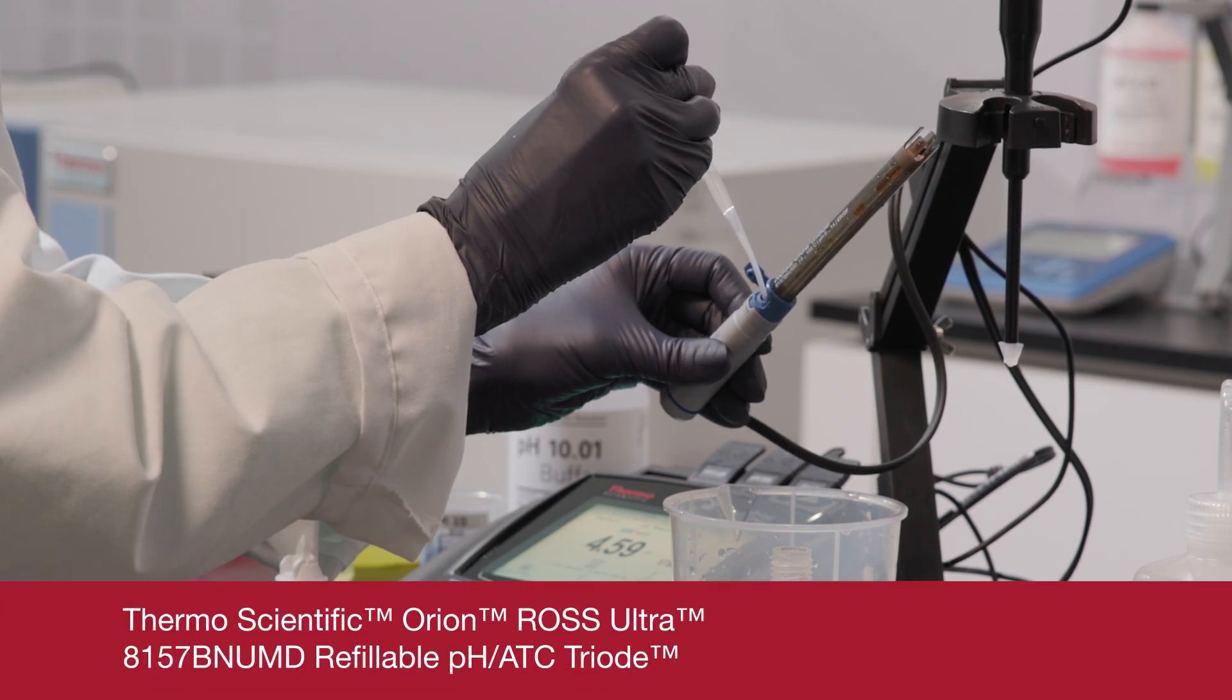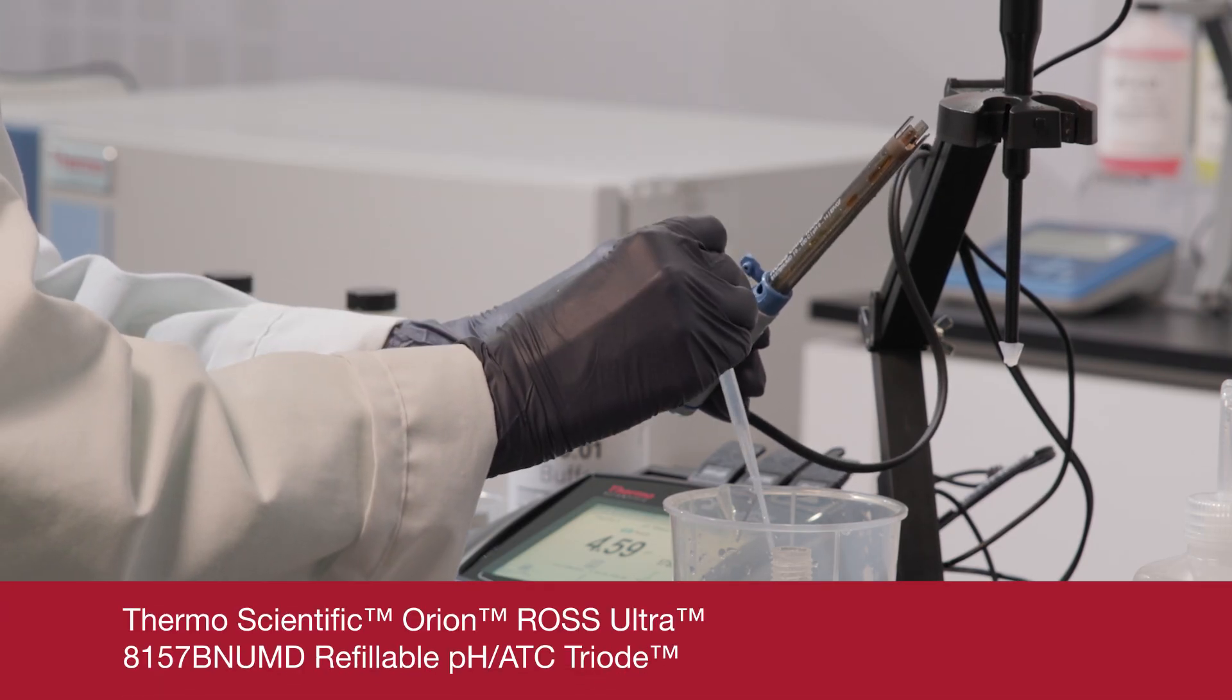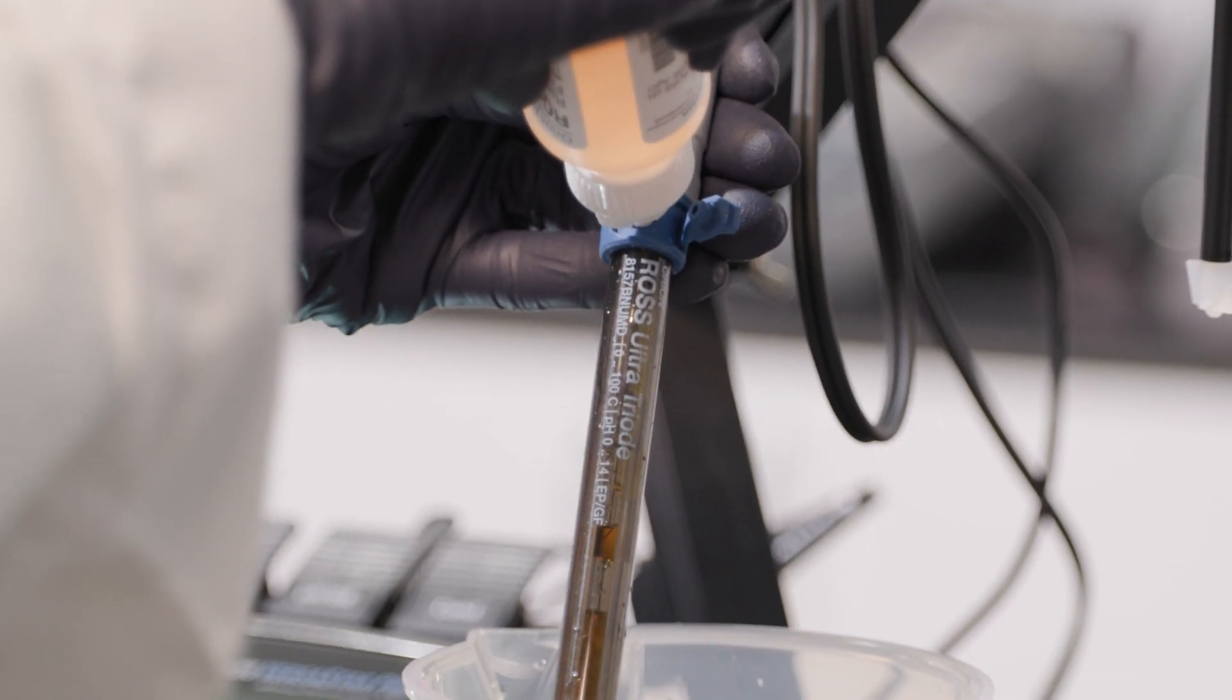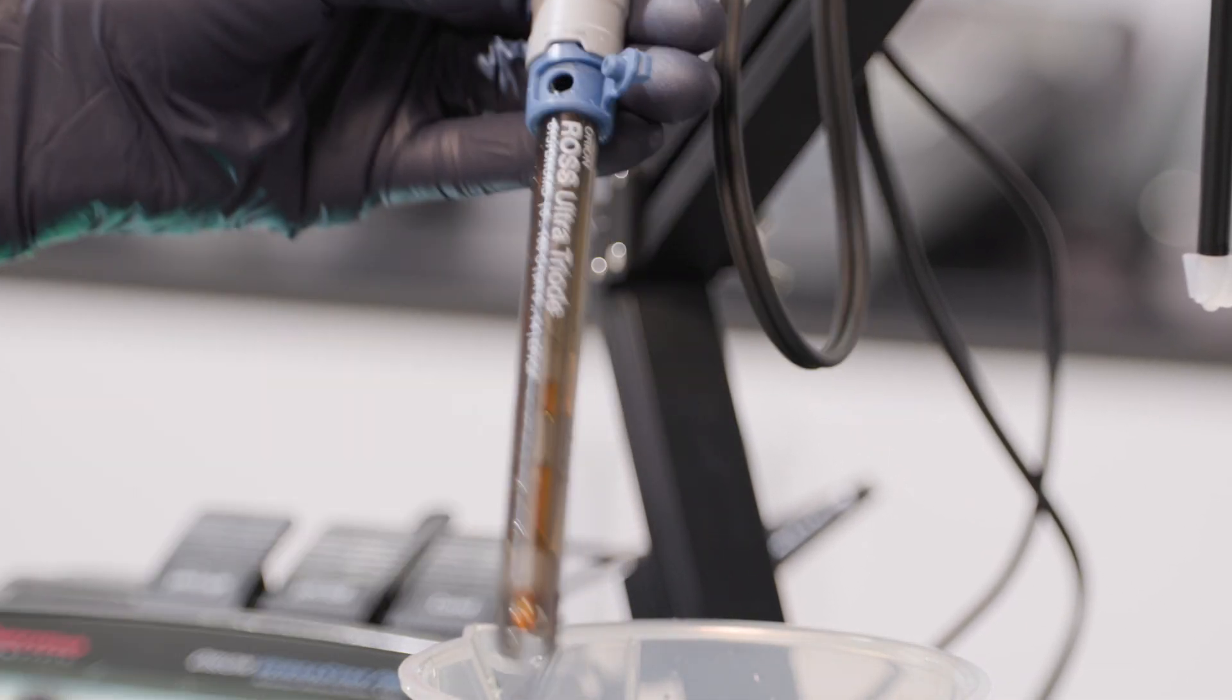For high-temperature samples, refillable electrodes are more suitable than gel-filled electrodes because the latter can be damaged. Refillable electrodes tend to last longer and have a longer warranty because they can be restored. An electrode's design will determine how easy it is to clean.